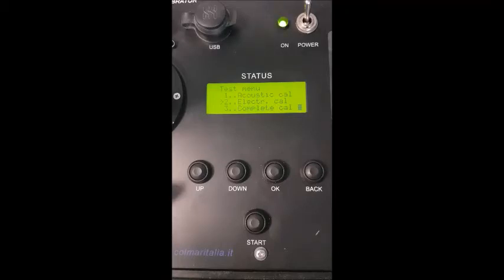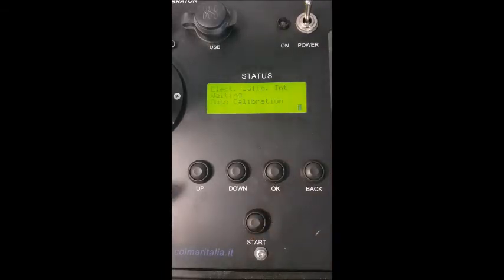and the data being collected enables the user to then build a curve of the sensitivity of the device. Similar to the acoustic test, an electric test can be performed as well. By accessing the electric calibration menu, the user first has to select whether he wishes to perform the test with an external signal or with the internal signal generator. The default is using the internal signal generator. The user then selects the start frequency of the sweep and the end frequency. The default is to start from 3 Hz and climb to 200 kHz. When start is pressed, the system automatically performs the electrical calibration.